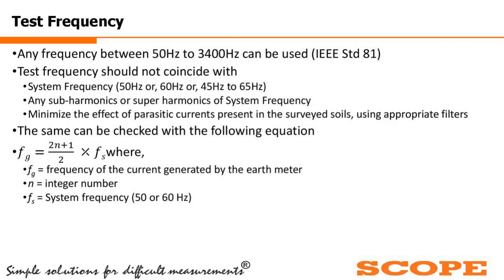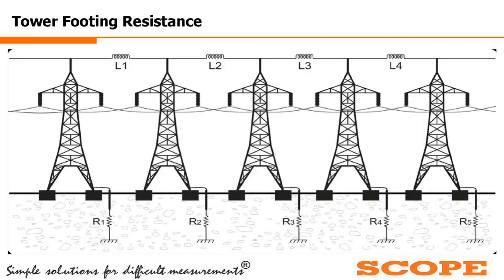That's the primary criteria, because nobody is going for the subharmonic zone, that very low frequency, because IEEE has said it should be anything more than 50 hertz. So I do not have to consider the subharmonics part. It always has to be superharmonics, on the higher side. So n should be an integer number. That's the check, we can say.